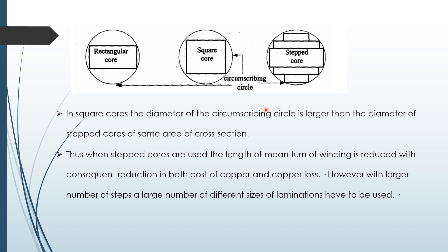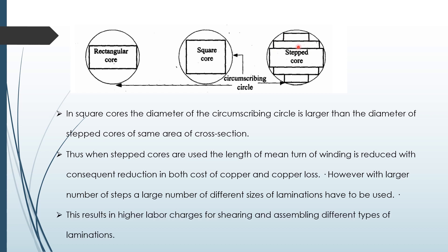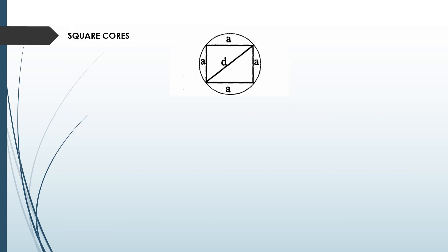However, a large number of different size laminations have to be used. This means that if you are using a step core, you need a number of laminations of different sizes, which will increase the cost of manufacturing but reduces the area wasted. This results in higher labor charges while laminations need to be stacked together, so assembling charges are also large compared with the square core and rectangular core.